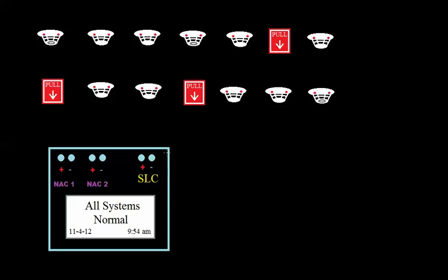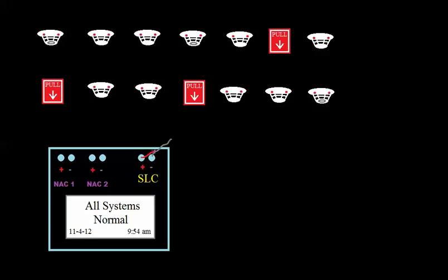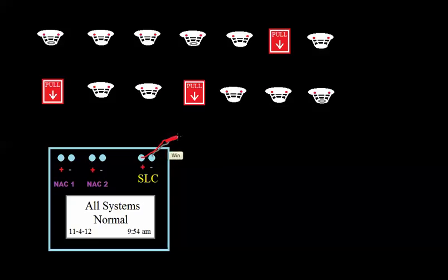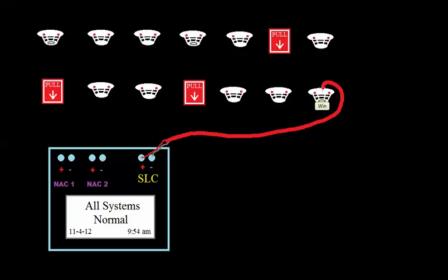Modules, there's a whole bunch of them, we'll get into some. But for right now, just look at the pull stations I've drawn here, and those would be modules. On some panels, it doesn't even really matter. Sometimes you're just limited to 50 devices total, whether they're devices or modules. Let's wire this up real quick. I'm going to do something a little bit different than I've done in the past, so you don't have to watch me draw all these two wires to each device. I'm going to draw these two little conductors, and they're going to go into a fire alarm cable, which is usually what you see in the field anyway.